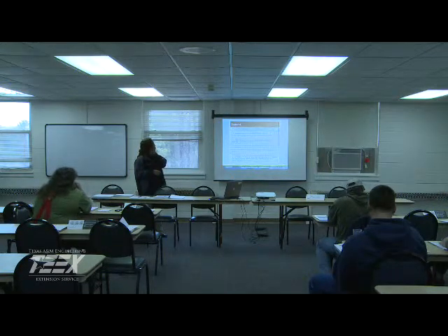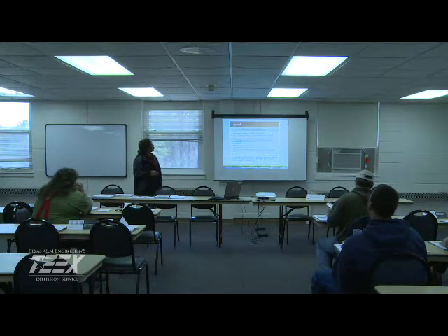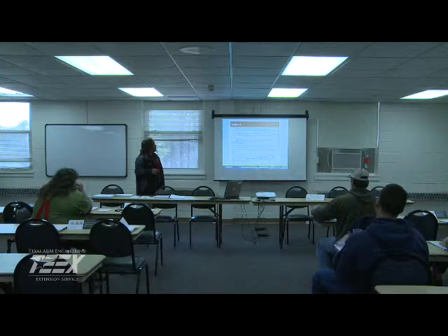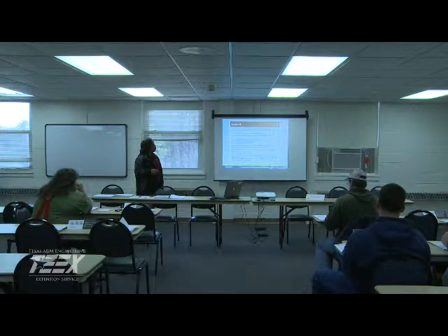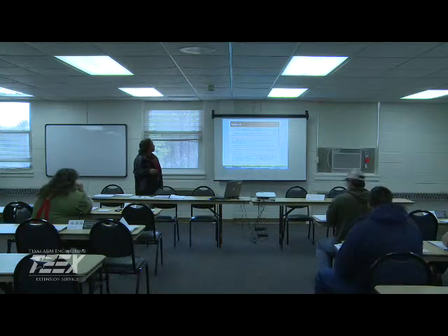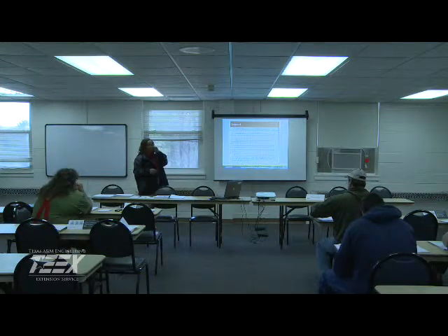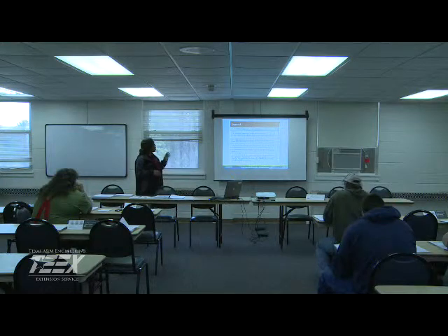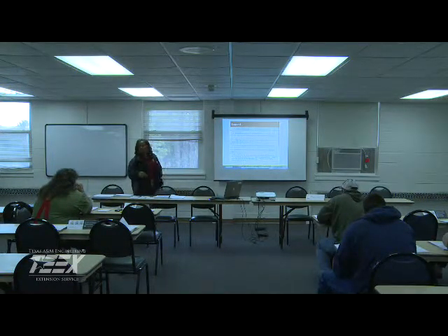All right, when you see 1 asterisk on this next chart, that means you're going to do 1 sample at the entry point to the distribution system. If you see 2, there are 2 quarterly samples at each, again, entry point. This will be for quarterly. Again, it's not in your book, but I'll give you the website where you can go and get this quick reference guide. And then X, no sampling is required unless your primary agency tells you you have to do it.